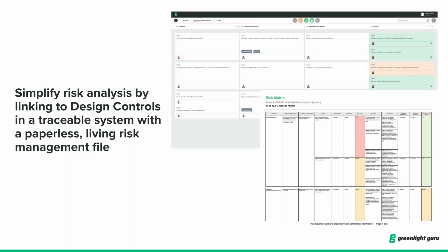I mean, that sounds like a risk activity, right? And then through design validation, you're proving that your product meets your user needs. In other words, from a design validation perspective, you're proving or demonstrating that you've designed the correct product. Also sounds a lot like risk. And I can't explain it, I don't understand it, but over time, there's been this whole spin-out of, oh, we have to do this whole other risk management set of activities. And I won't get into all the details on that. Suffice it to say, though, that it is expected today.